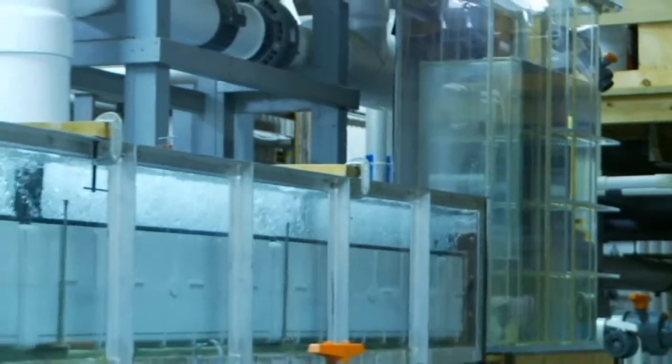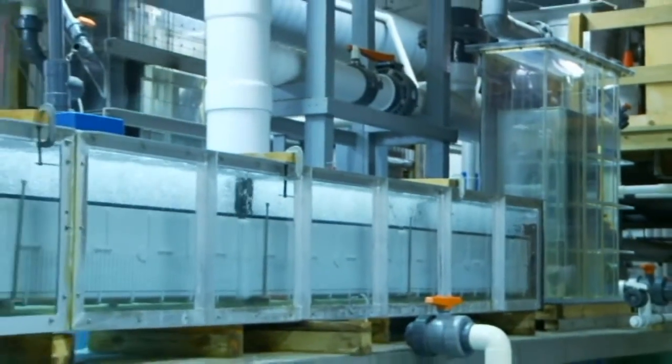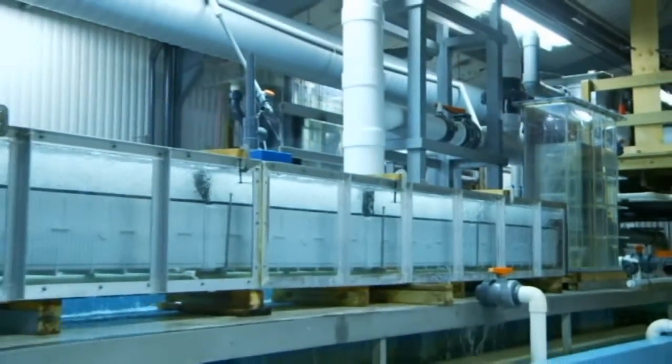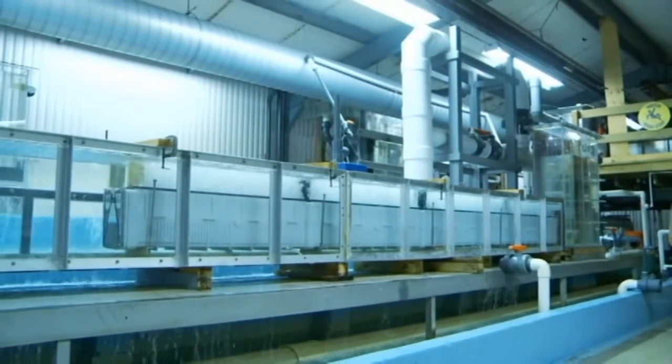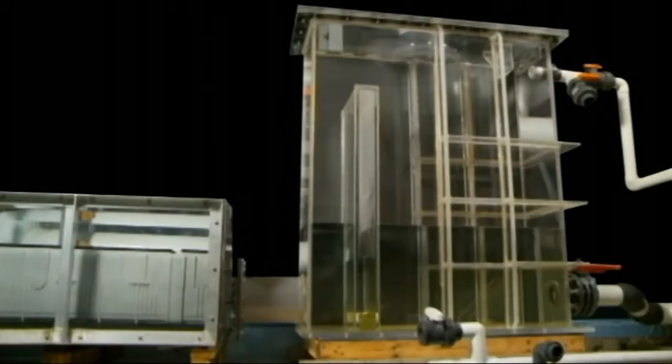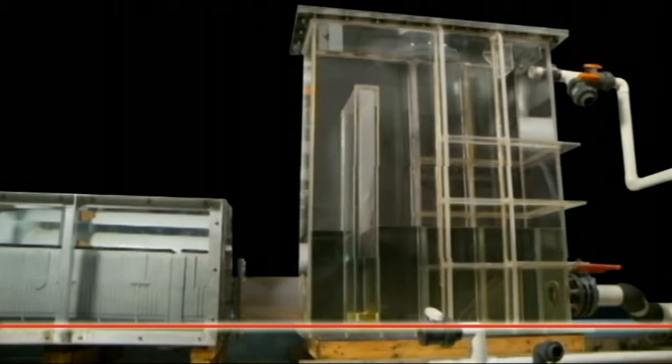This full-scale plexiglass model simulates a Leopold flat-bottom flume filter with one lateral. The flume on the right is called a flat-bottom flume because the flume is located at the same elevation as the filter floor. It requires no additional excavation that front, center, and H flumes require, so it is more cost-effective to build.